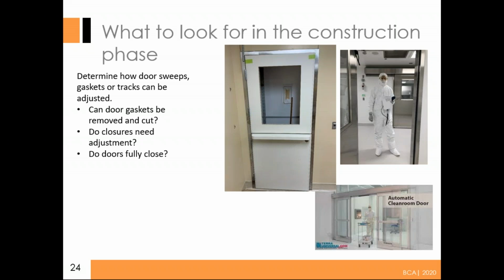We talk about the tightness of the rooms. We like to have the room start as tight as possible, but a lot of times we've got to loosen it up when we're doing the balancing or the pressurization. We'll do it by adding more gap across the bottom of the door, or we'll pull the door right off, pull the gaskets out of the door, cut the gaskets and slide them back in. That's some of the ways we do a lot of our clean rooms, especially with cascading pressurization.